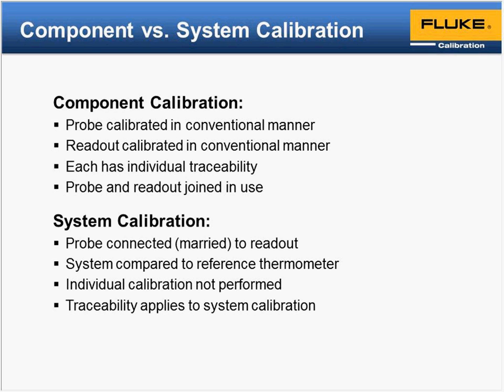So a component calibration: the probe and the readout are calibrated in a conventional manner. Again, in our examples that we went through, most of the time things were together as a system for the heat source calibration and the heat source against the reference. The only time that we broke it apart was in the initial one with the simulation. So with a component, what was not shown there is the probe would go off and be placed through its own routine where we would plug into another readout. Typically, it would go to a reference. Some adjustments would be made, or a polynomial fit, or we would ensure that it's conforming to a DIN class curve. As you put each piece back, you now know, okay, my RTD probe is behaving how it's supposed to, and my readout electronics are adjusted within the tolerance they're supposed to be good at.